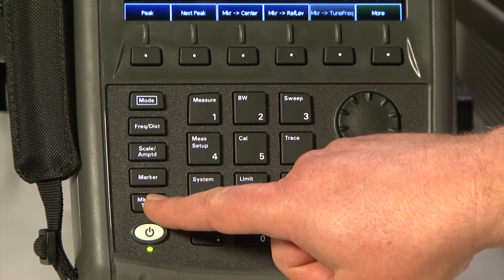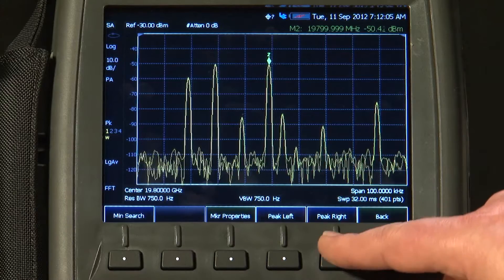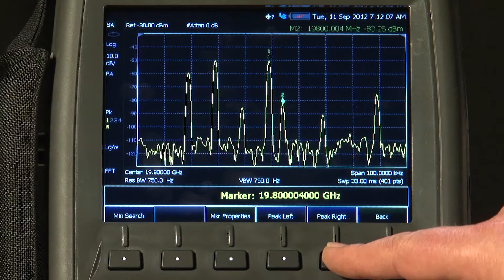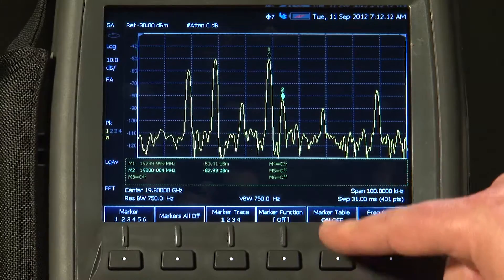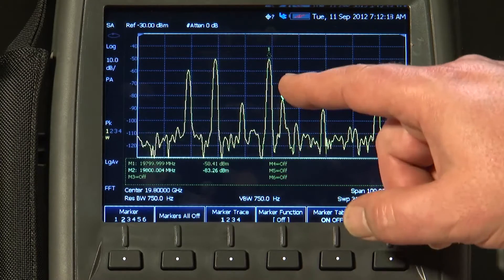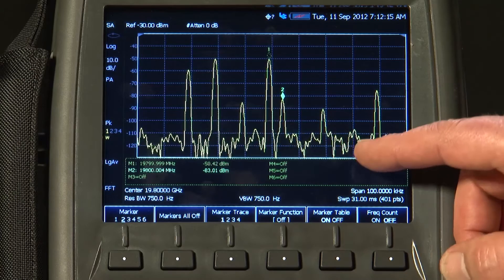Marker 2, more, peak, right. So we can turn on up to 6 markers. And we can even turn on a marker table to display the frequency and amplitude values of all 6 markers.